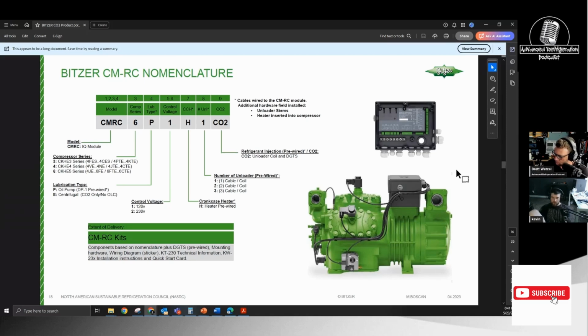Going through there, you got to program the model and serial of the compressor, choose that, and then tell it if it has Varistep unloading, and then tell it if it has liquid injection or not. It'll enable the liquid injection because it has its own terminals for that, where it supplies the control power from there. After that it was pretty simple, just, okay, what is the minimum compressor capacity? If it's 2 coils, if you've got 2 heads on a 6-cylinder, 33% is the minimum.